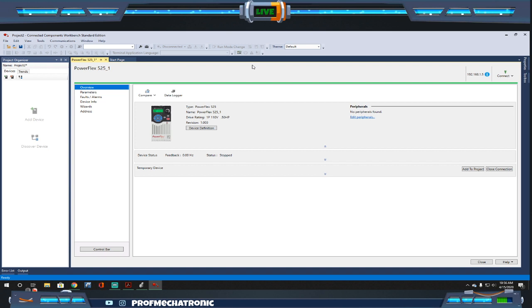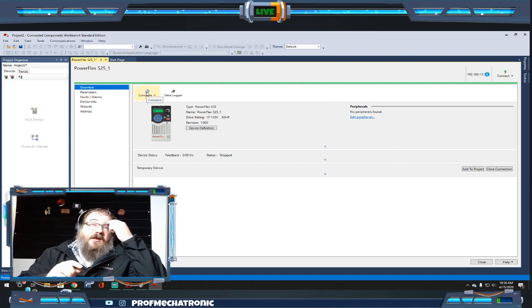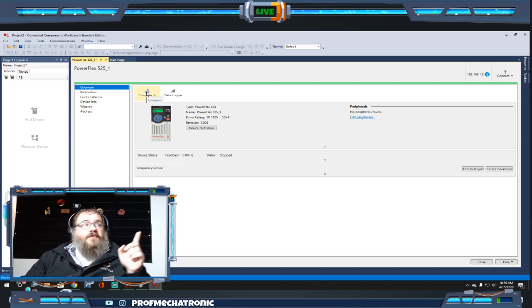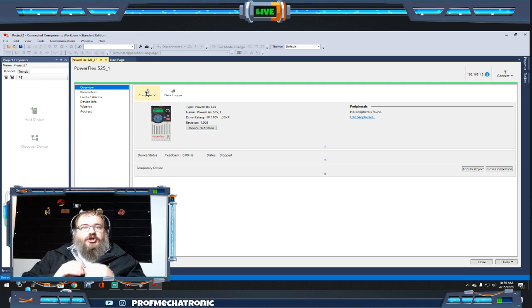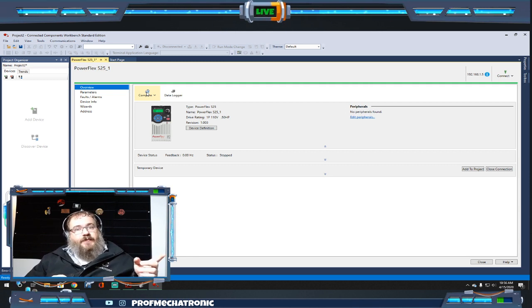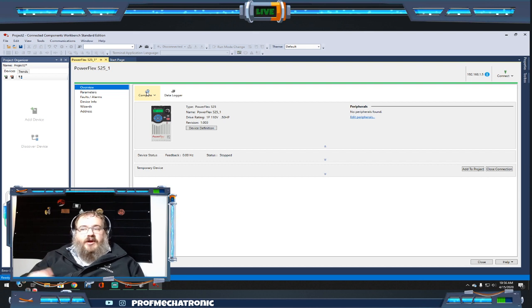You absolutely can. The key to setting them up that way is to configure your IP addresses on the drive itself. Studio 5000 has no way of pushing an IP address to the actual drive without having that drive set up. So you have to go through manual configuration using C128, C129, C130, 132, 133, all the way up to actually set your IP addresses.